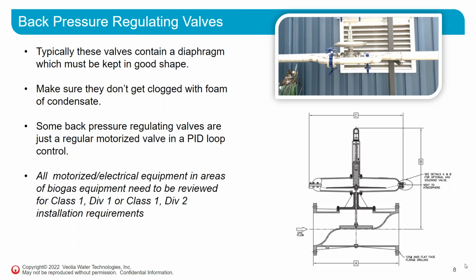The back pressure regulating valves are used to control the back pressure, which is relevant to the pressure in your reactor space. It's important that they don't get clogged with foam or condensate, especially the sensing lines, because they might not operate as designed. Most of the back pressure regulating valves are typically just a diaphragm. They can also be a motorized valve with a PID loop control, but it's important to note that any motorized or electrical equipment in areas with biogas needs to be reviewed and most likely qualifies for Class 1 Division 1 or Class 1 Division 2 installation requirements, which is pricey and more complicated. So diaphragm valves are the most common.